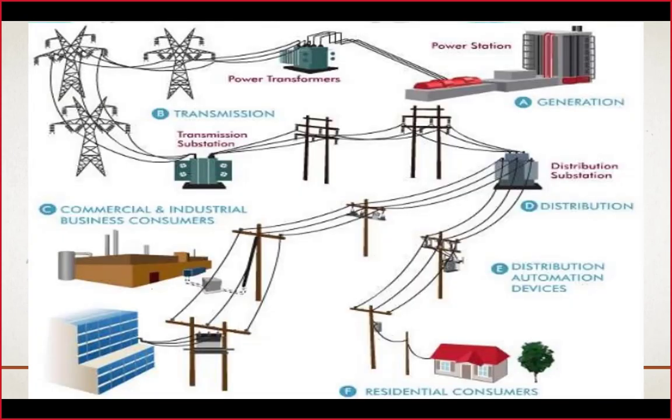I have taken a pictorial view of the power system starting from a generating station, and all the transformers that exist in our system are present here in this diagram. Here the first transformer is a generating transformer. Remember its low voltage side will always be delta, high side will be Y grounded, and here is the vector group. It will be YNd1. Capital N shows that this neutral is on high side. So high side is Y, low side is delta, and low side is lagging behind high side by 30 degrees. This is the vector group.